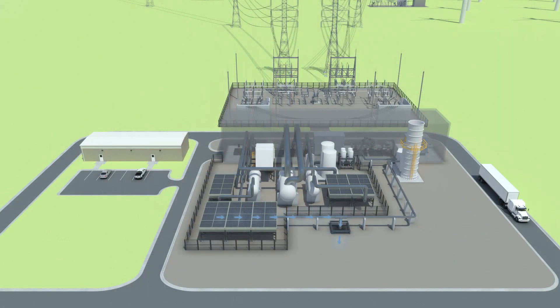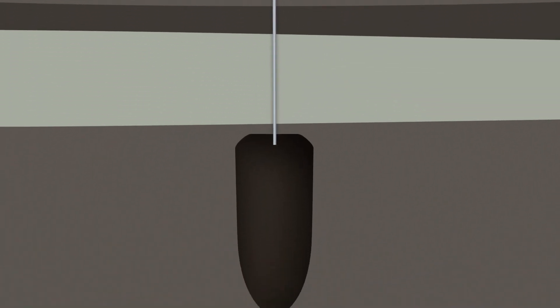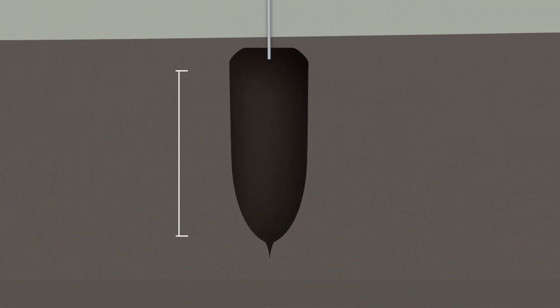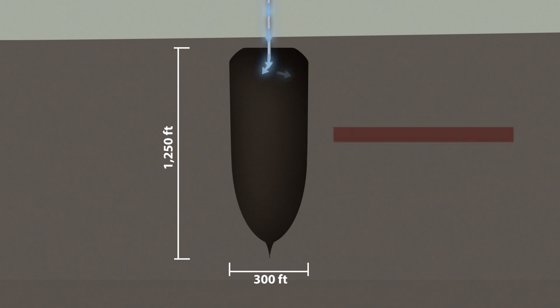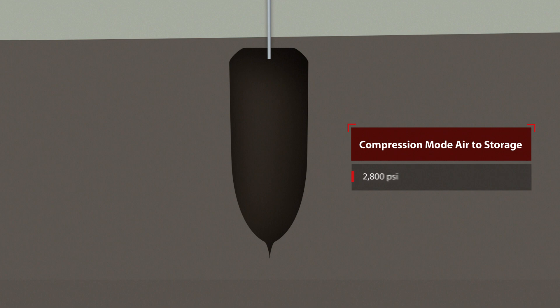The compressed air is then pumped into a massive cavern, large enough to house the Empire State Building. The process of filling the cavern is called compression mode. At full charge, the cavern air pressure can reach up to 2,800 pounds per square inch.